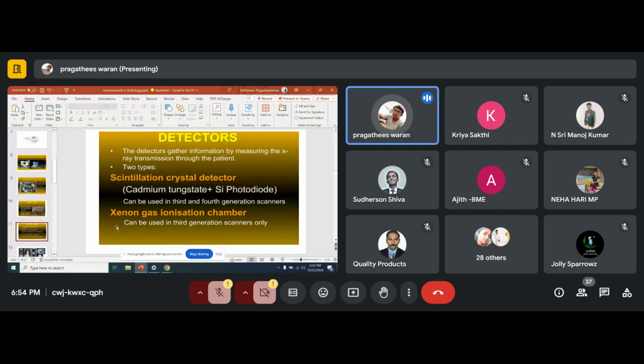In olden days, they used xenon gas ionization chambers, but the accuracy of producing images with them is very low. The image won't be that clear, but we could still get some images that the doctor could use for diagnosis. Then slowly it was converted to scintillation crystal detectors. Currently we are using scintillation crystal detectors, for example cadmium tungstate, and silicon photodiodes.